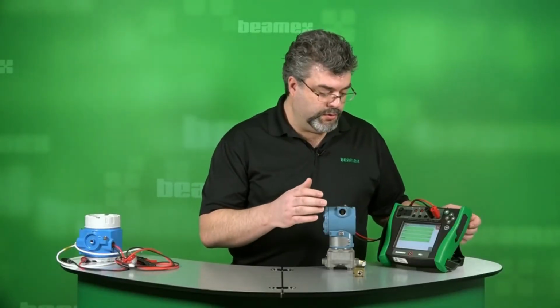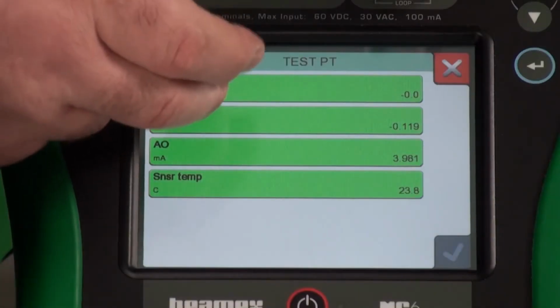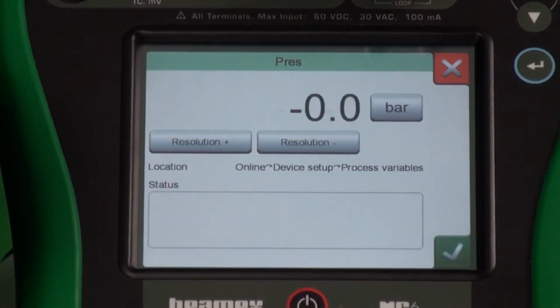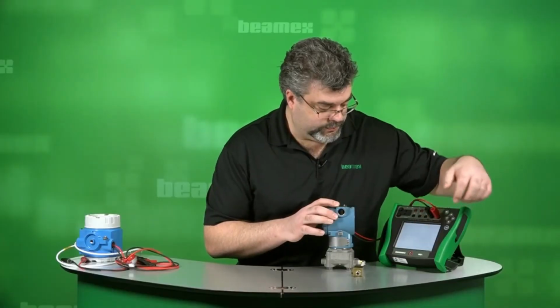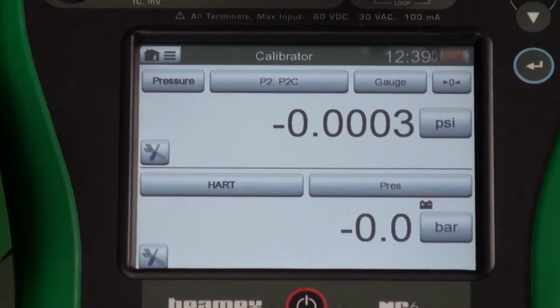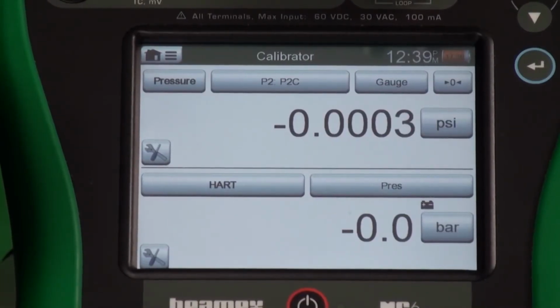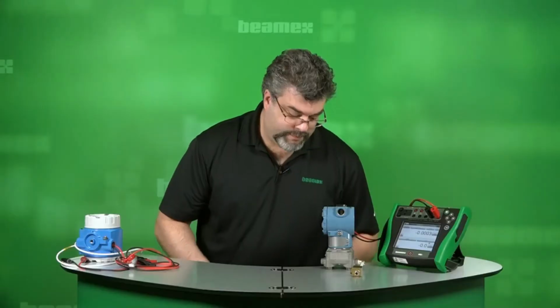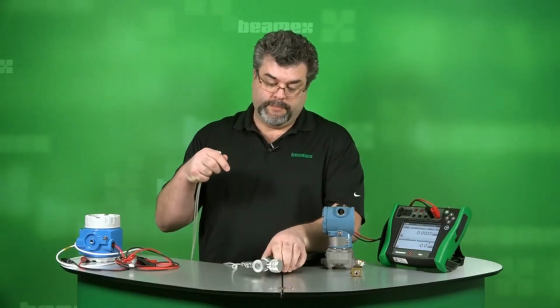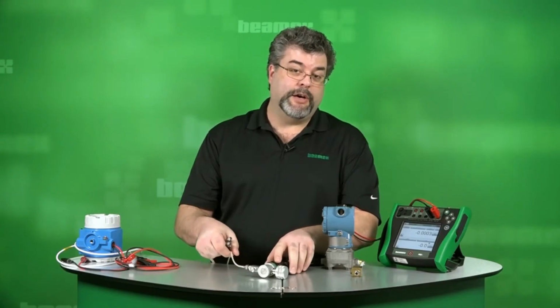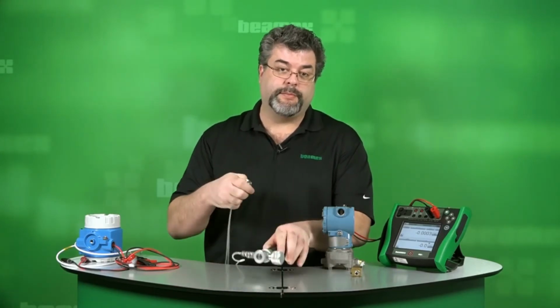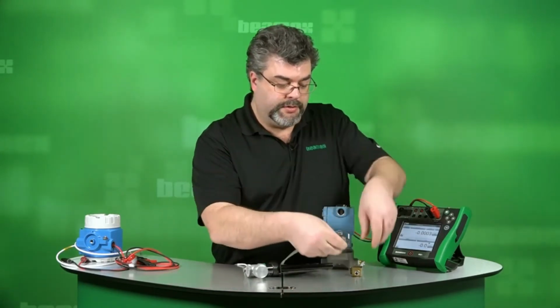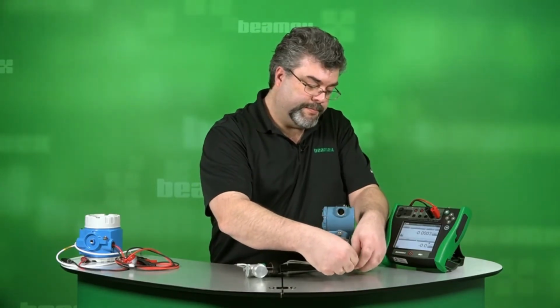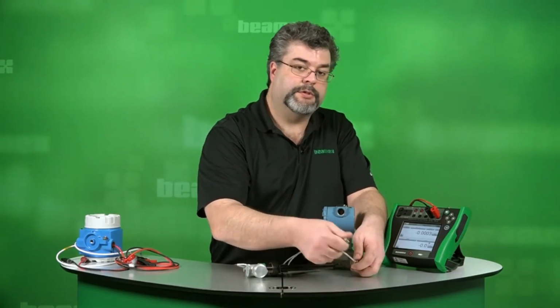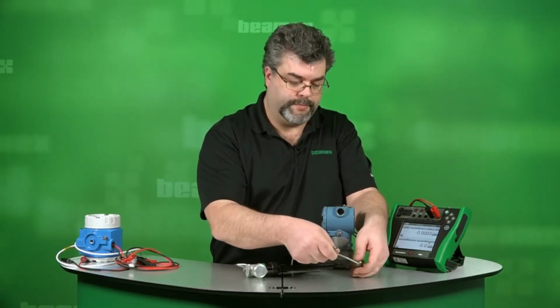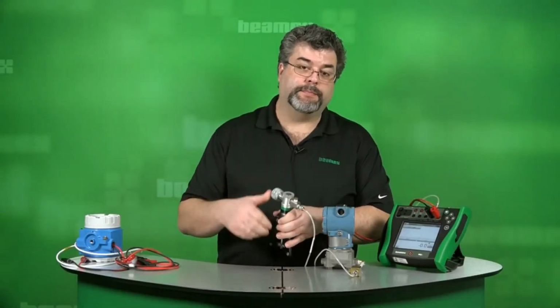If we wanted to look at pressure, we've selected our output for pressure. Now let's manipulate it. I have a pressure pump with 3 connectors and a T-hose in the middle. So I've got a connection on my pressure pump. We have one connection for the pressure transmitter. And the third leg we'll put on the pressure port on the calibrator. So here's our output on the bottom.